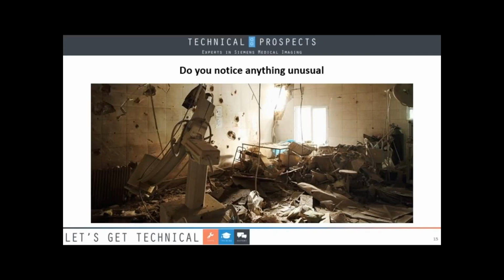All right. Once you're done with that, what do you see when you enter the scan room? Is anything out of place? Is there fluid on the floor? Is the room temperature good? Some medical equipment will not function properly if the room doesn't have a specific temperature or humidity. MRs and CTs especially, but some other stuff, it just won't work. And you'll spend a lot of time and you won't understand. And so sometimes it's just good to check the temperature when you walk in.